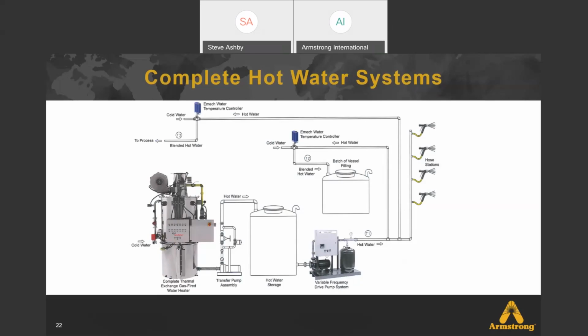And again, most of the water generated by direct contact addresses the washdown needs in place. So certainly there's going to be hose stations that it feeds. It also then, if some process requirements are acceptable using the direct contact water, then there's additional batch vessels, perhaps in other blending of that water to meet other temperature demands. So this just kind of gives you an overview of a typical hot water system using direct contact heaters.